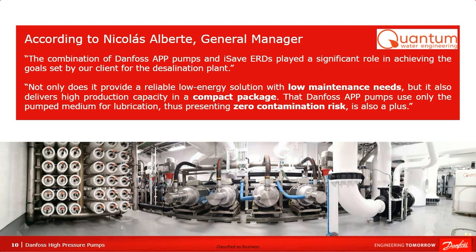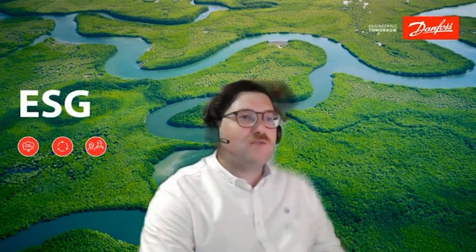Operating conditions are important, but they are even more critical on a ship. Ships move around, seawater temperature varies during the year, and salinity differs depending on how far from shore the ship is. By using our pumps and iSave devices, which are volumetric systems, the system can adapt to any operating condition — whether the seawater temperature goes 10 degrees higher or lower, or recovery needs to be adjusted — all by pushing one button.